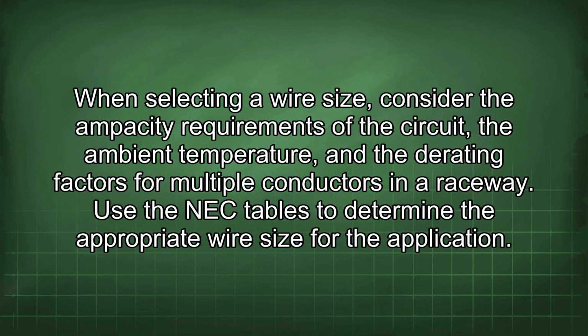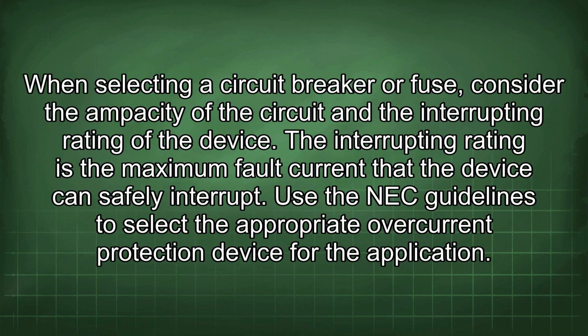When selecting a wire size, consider the ampacity requirements of the circuit, the ambient temperature, and the derating factors for multiple conductors in a raceway. Use the NEC tables to determine the appropriate wire size for the application. When selecting a circuit breaker or fuse, consider the ampacity of the circuit and the interrupting rating of the device. The interrupting rating is the maximum fault current that the device can safely interrupt. Use the NEC guidelines to select the appropriate overcurrent protection device for the application.